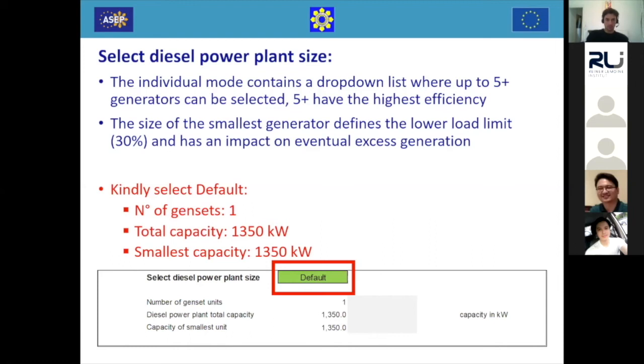And also the lower load limit of the generators is set to 30%. So this means the generator has to run at minimum 30% of the rated capacity, because otherwise it would be damaged.